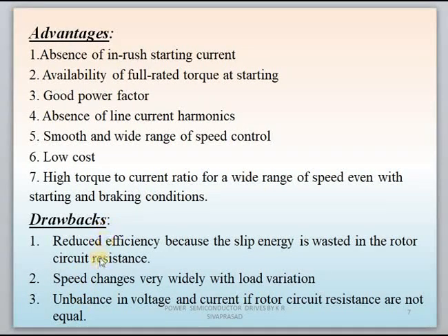And the drawbacks: reduced efficiency, because the slip energy is wasted in the rotor circuit resistance. This is a major drawback here. The wastage of energy is coming through the rotor resistance, and due to that, efficiency reduces. And the speed changes very widely with load variation. That is one more drawback here.